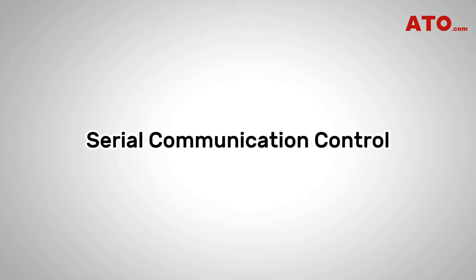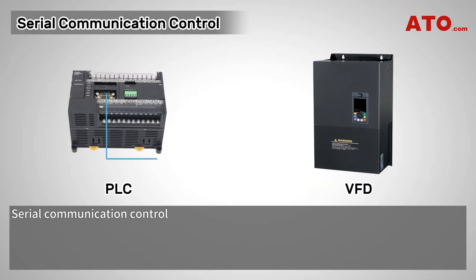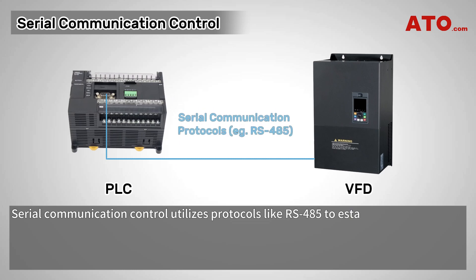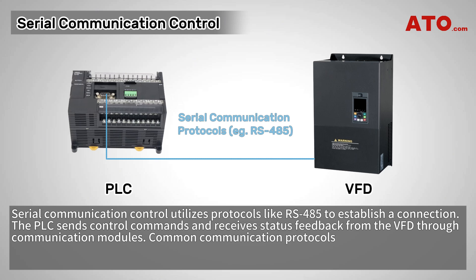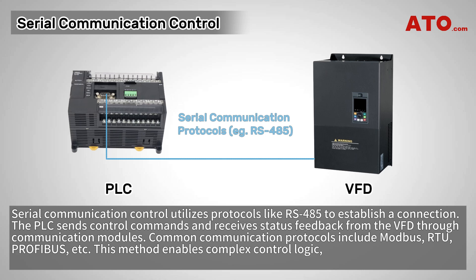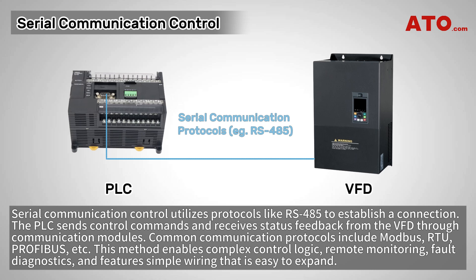Third is Serial Communication Control, which utilizes protocols like RS-485 to establish a connection. The PLC sends control commands and receives status feedback from the VFD through communication modules. Common communication protocols include Modbus, RTU, and Profibus. This method enables complex control logic, remote monitoring, and fault diagnostics, and features simple wiring that is easy to expand.